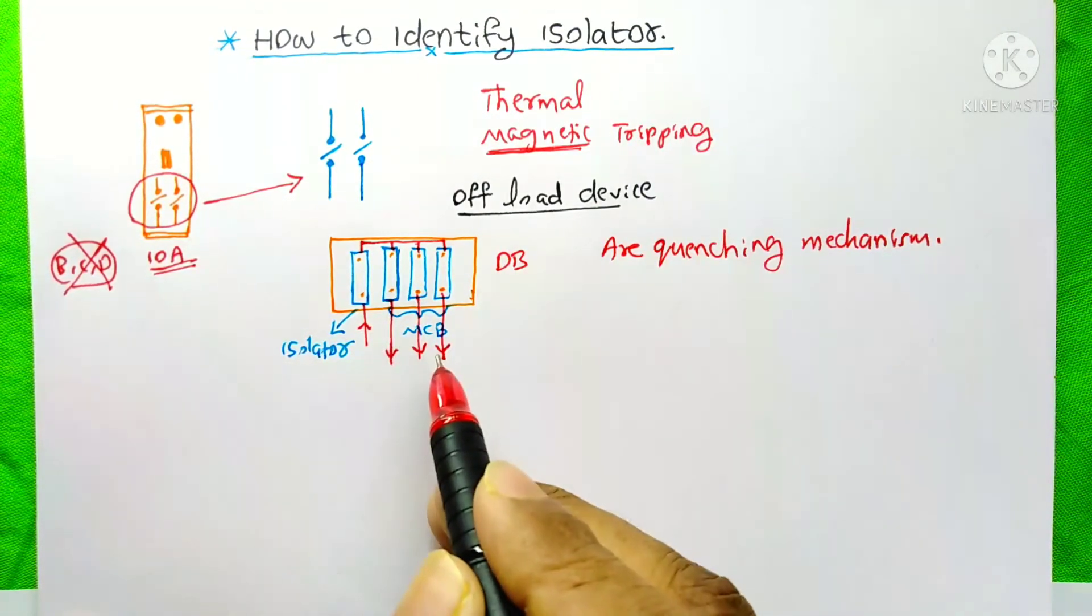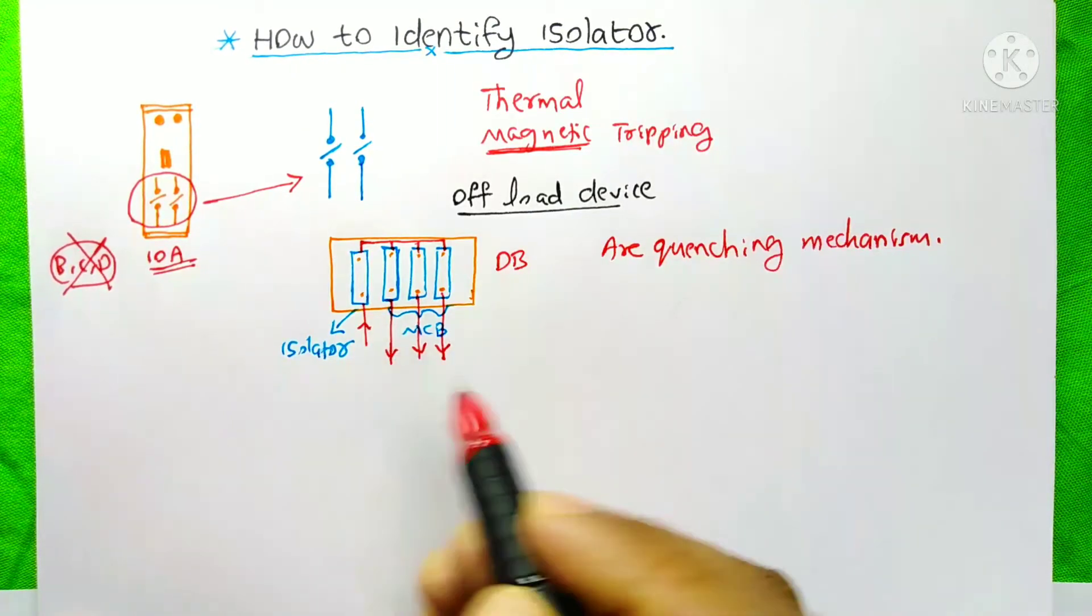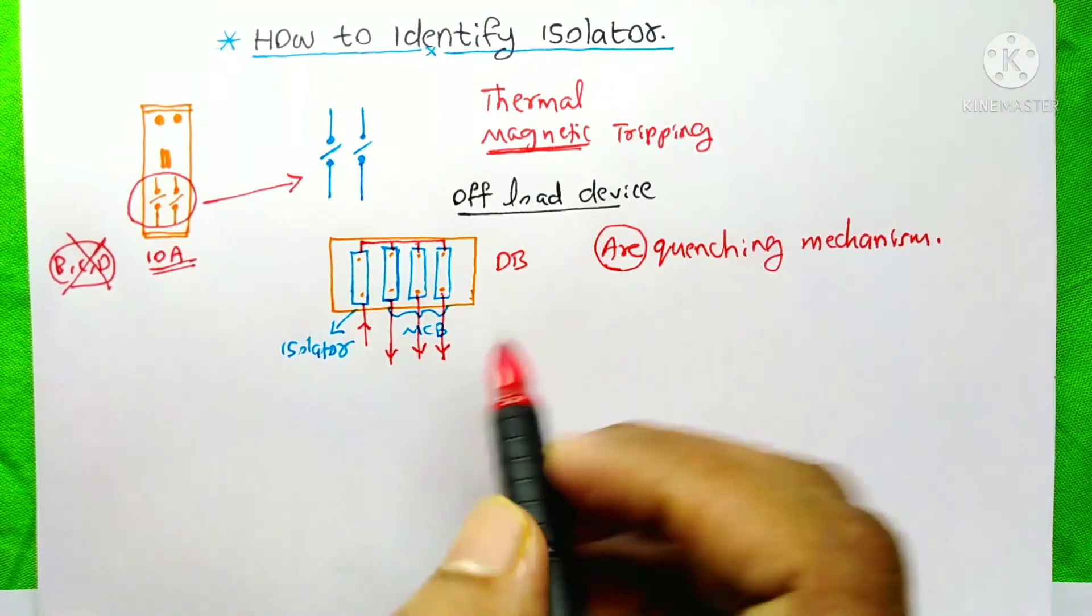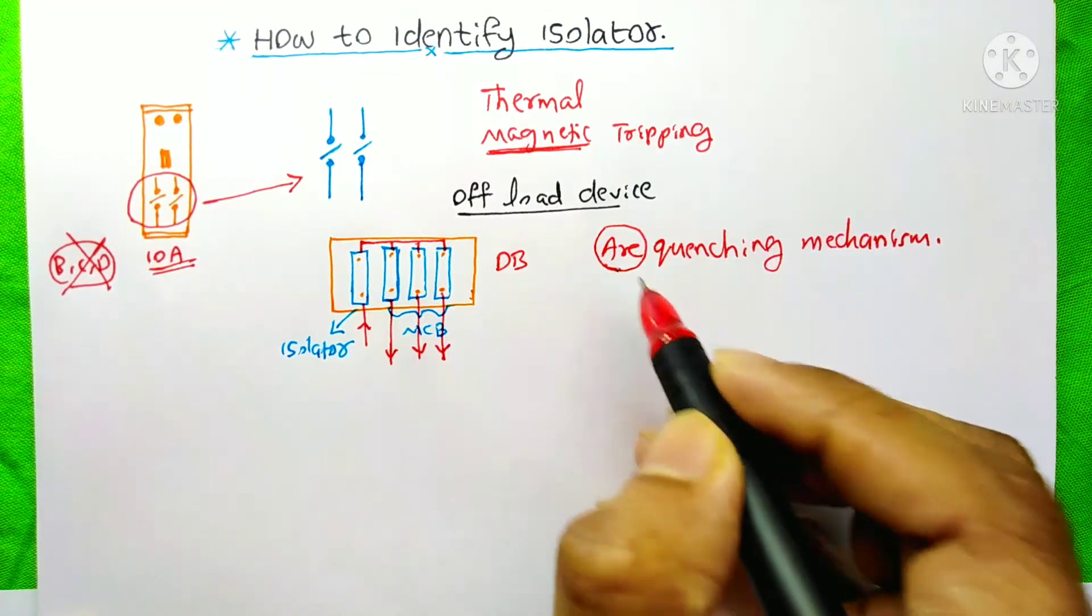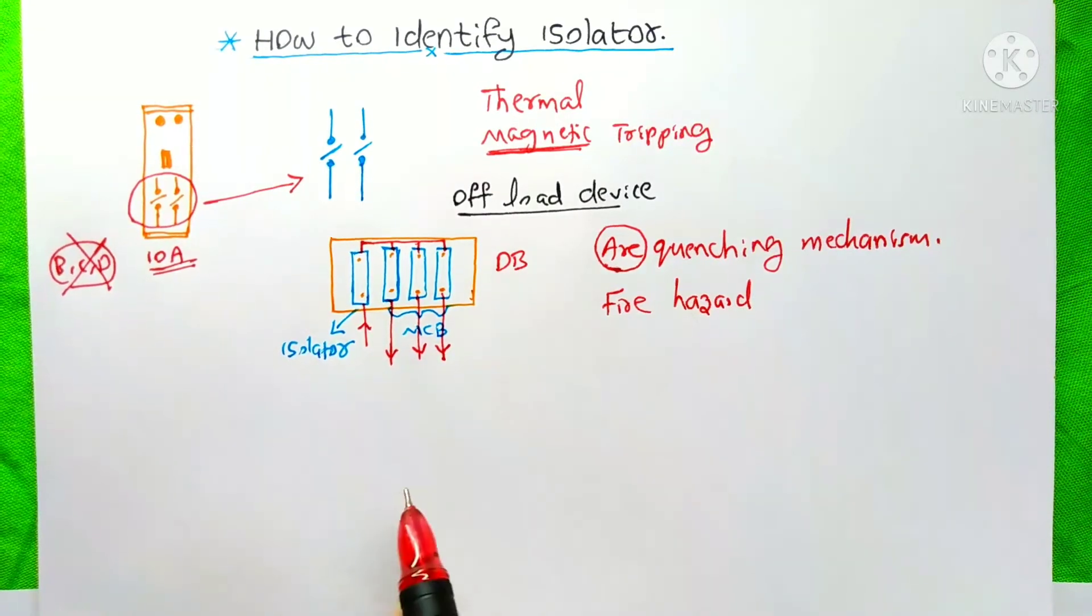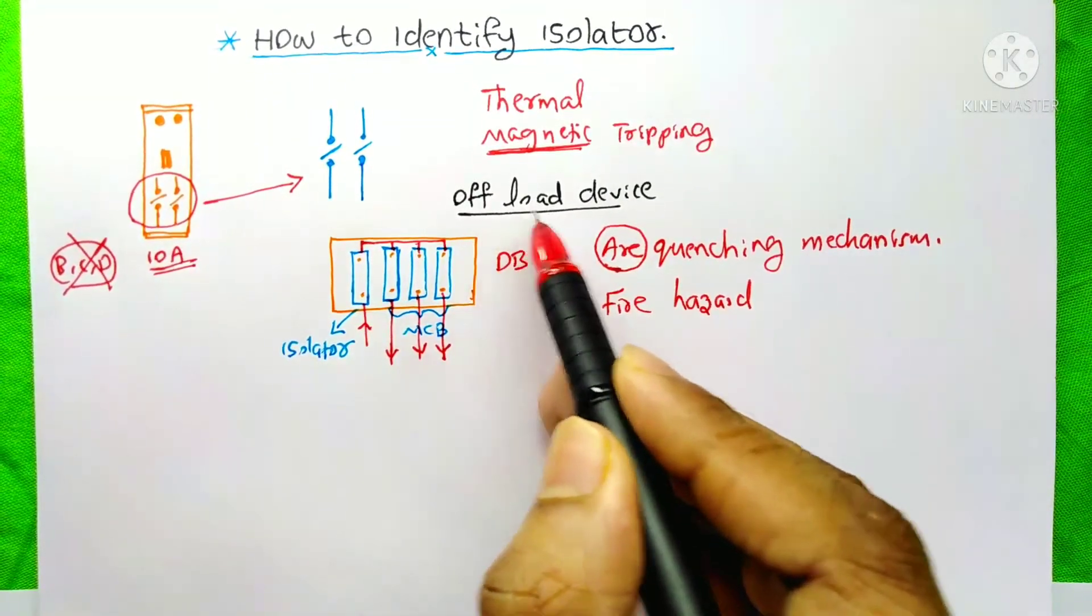If the current is existed on both sides of the isolator, that means at the condition of when the loads are on the running, at that time if you switch off this isolator, then at that time the arc will be formed and it will cause a fire hazard. That's why we call it as an off-load device.